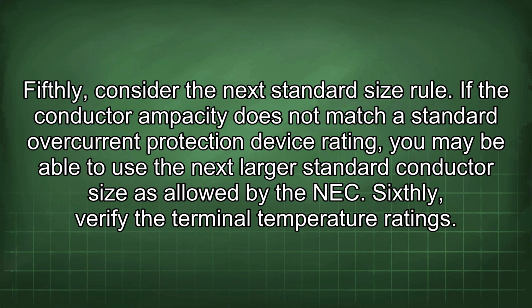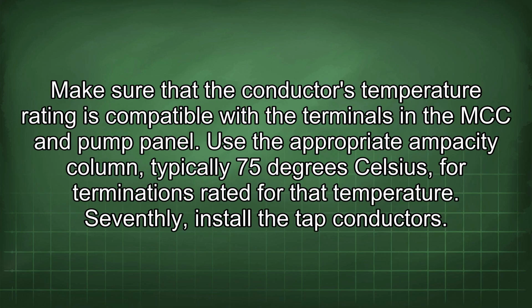Sixthly, verify the terminal temperature ratings. Make sure that the conductor's temperature rating is compatible with the terminals in the MCC and pump panel. Use the appropriate ampacity column, typically 75 degrees Celsius, for terminations rated for that temperature.